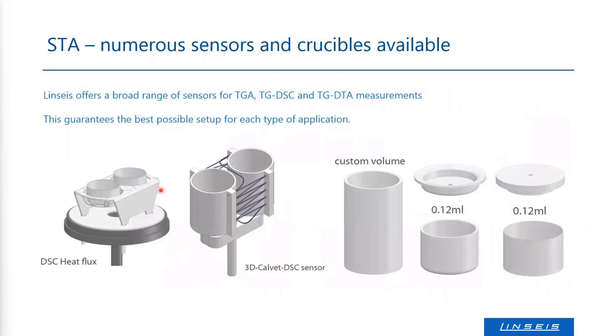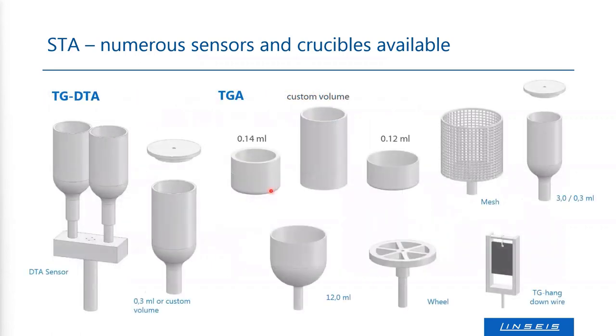Here are some sample holders for combined TG-DSC or TG-DTA measurements, depending on the sensitivity needed for the DSC signal. We have not only the classical heat flux type, but also the Calvet-type system using larger crucibles with multiple thermocouples and thermopiles which ensure higher sensitivity. For pure TGA measurements, we have large crucibles up to 12 milliliters or mesh-type sample holders.